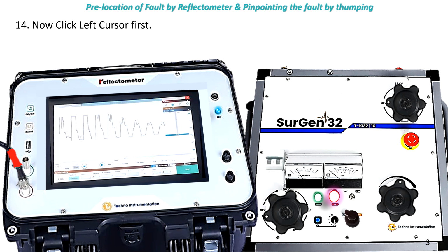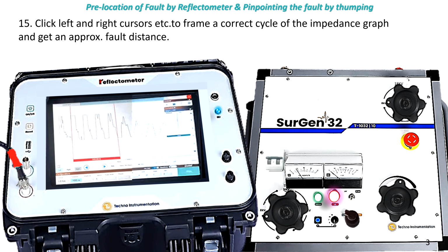Now click the left cursor first. Click left and right cursor etc. to frame a correct cycle of the impedance graph and get an approximate fault distance.